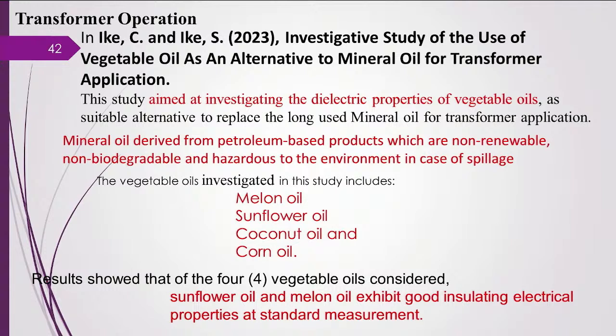In this research, because of the nature of the oil contained in transformers and RMUs, which are not environmentally friendly, hazardous, and non-biodegradable, and since they stay on the ground for a long time and can burn, we tried to find an alternative to transformer oil. We investigated four vegetable oils: melon oil, sunflower oil, coconut oil, and corn oil. We found that sunflower oil and melon oil exhibited good insulating electrical properties at standard measurements.